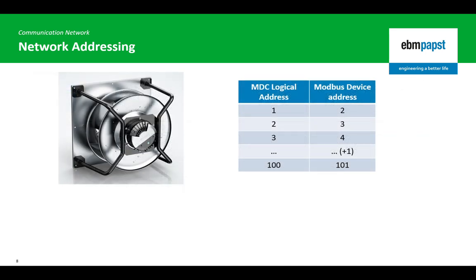The MDC controller assigns two identifiers for each fan in the array: the logical address, which can reflect the physical position of the fan in the array, and the Modbus device address, which the fan responds to when sent a command by the MDC controller.